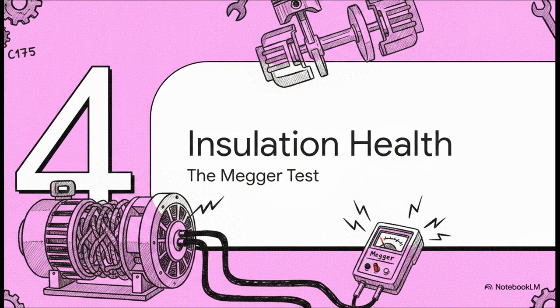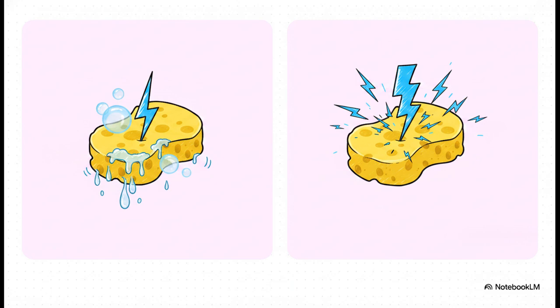Okay, bringing us to Section 4, testing insulation health using the Megger test. We're stepping away from fluid dynamics and electronic control for a minute, and we're going to look at testing the overall electrical health of the generator itself, specifically the stator windings. To really grasp why a Megger test is so vital, especially for those standby units, think of a damp sponge versus a bone-dry sponge. If you touch a low-voltage circuit to a damp sponge, it conducts a small trickle of electricity pretty easily, right? But a completely dry sponge blocks that electricity entirely.